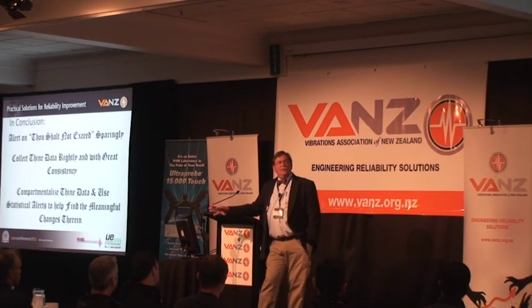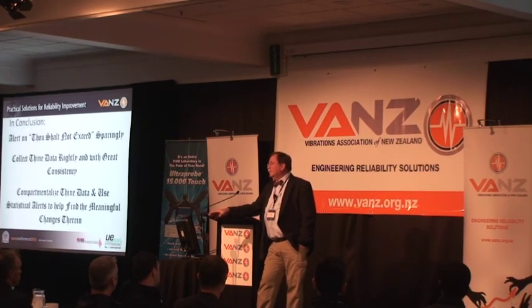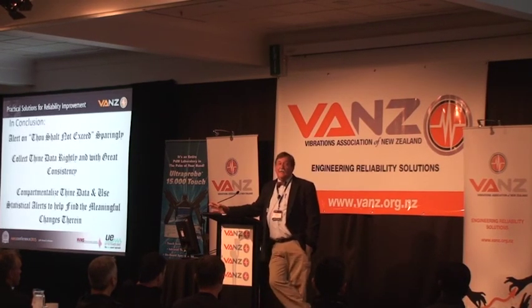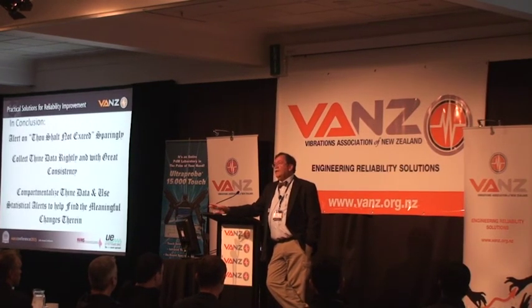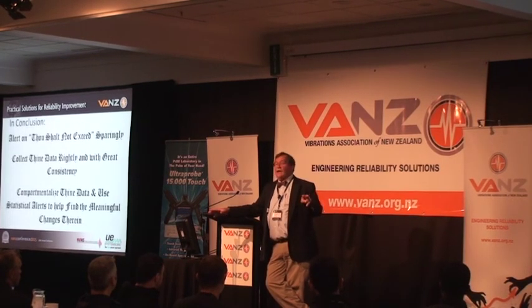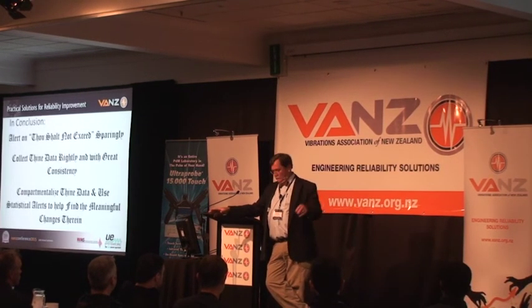That machine was identical to a number of machines in other parts of the world where they operate on 50 hertz power. They got the machine for a good price, it was available. I truly don't think anybody paid close enough attention to the fact that every other use of that machine, except for two, was on 50 hertz. There were two others put into the US, and they had similar problems.